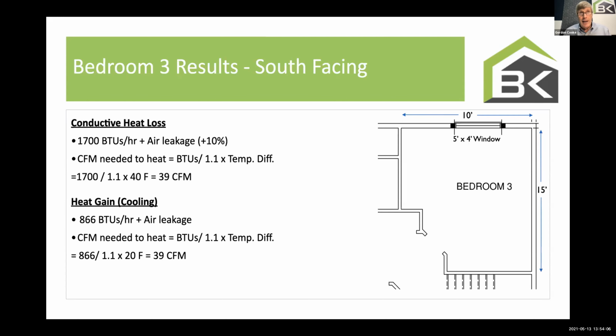And then you're going to, well, I got to add air leakage. Right. And here's what most heat loss heat gain programs do. They take the total air leakage for the house and apportion it fairly evenly to individual rooms. That is, they take the percentage of heat loss of the house and assign that to air leakage. I'm not explaining that very well.